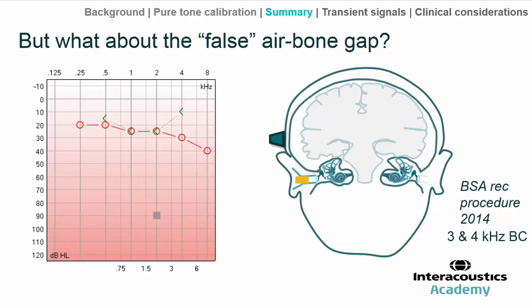Having discussed the general principles, I'd like now to turn to one of the common clinical challenges which we face, which we could label a calibration issue or calibration challenge, and that's known as the false air-bone gap. When we perform air and bone conducted pure tone audiometry, we know as audiologists that some air-bone gap is inevitable even in patients who are either normally hearing or with a hearing loss that's sensorineural but no reason at all to think that they have a conductive component.